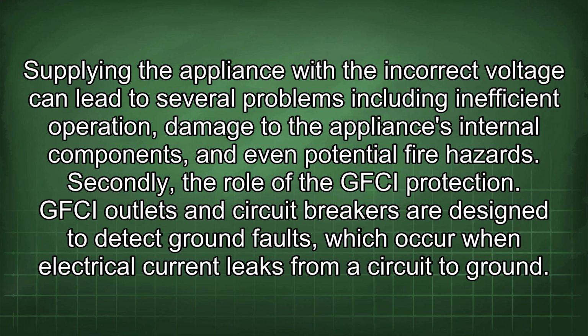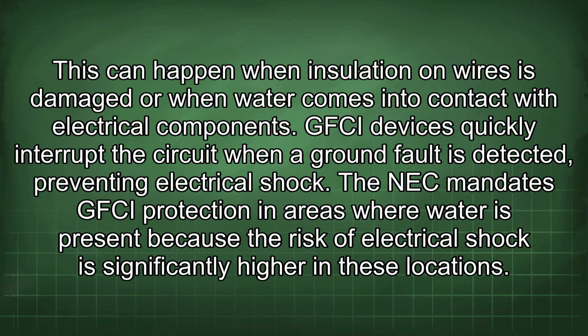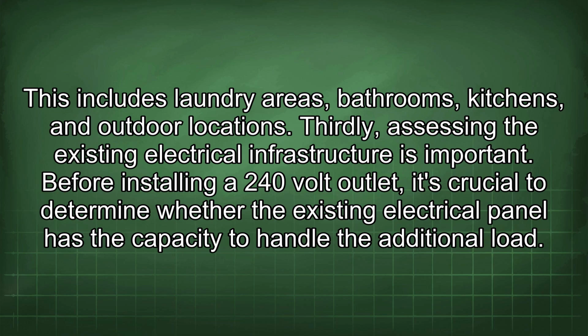Secondly, the role of the GFCI protection. GFCI outlets and circuit breakers are designed to detect ground faults, which occur when electrical current leaks from a circuit to ground. This can happen when insulation on wires is damaged or when water comes into contact with electrical components. GFCI devices quickly interrupt the circuit when a ground fault is detected, preventing electrical shock. The NEC mandates GFCI protection in areas where water is present because the risk of electrical shock is significantly higher in these locations. This includes laundry areas, bathrooms, kitchens, and outdoor locations.